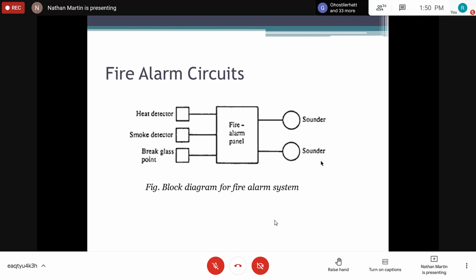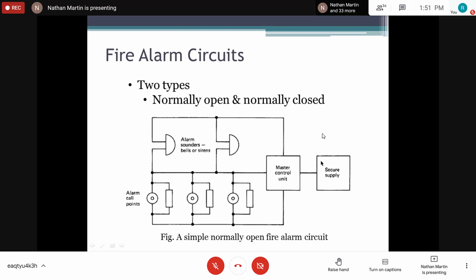So moving on, this is basically the diagram of a fire alarm circuit, the typical block diagram. So we have our sensing devices such as your heat detector, your smoke detector, your break glass point, and we have the control panel, right? And we have the sounders, right? So if any one of these sensors is activated, then the control panel will sound, right? They can be programmed to give a local alarm or a non-local, an entire facility alarm, such as the ones that are installed at UTEC, right?